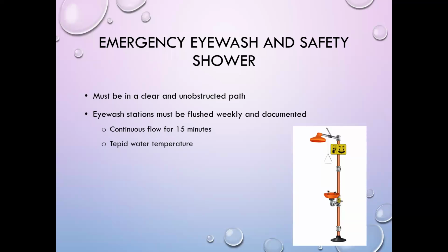All right, laboratories are required to have at least eye wash stations. And if they have showers, they are required to check those showers to make sure they're working properly as well. Any laboratory personnel can do this. They don't have to be done through inspection, but they do need to be checked weekly to make sure that they're flowing correctly. They should be checked by allowing the water to flow for 15 minutes.